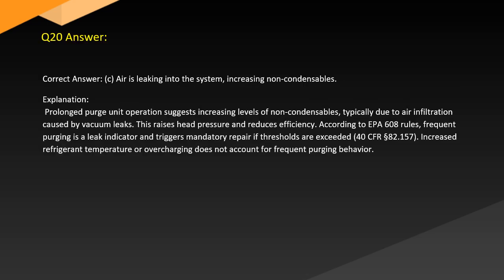Answer. Correct answer, C. Air is leaking into the system, increasing non-condensables. Explanation. Prolonged purge unit operation suggests increasing levels of non-condensables, typically due to air infiltration caused by vacuum leaks. This raises head pressure and reduces efficiency. According to EPA 608 rules, frequent purging is a leak indicator and triggers mandatory repair if thresholds are exceeded, 40 CFR 82.157. Increased refrigerant temperature or overcharging does not account for frequent purging behavior.